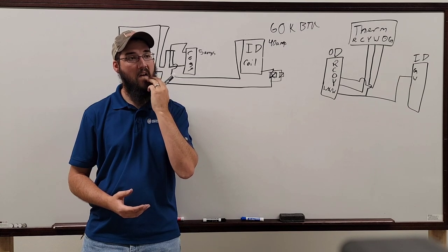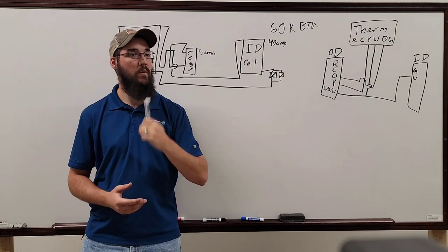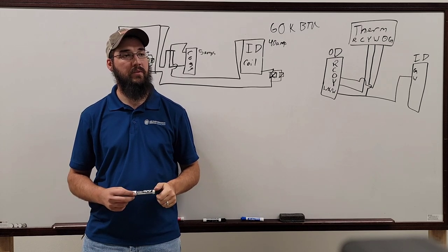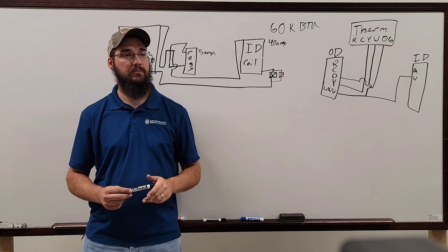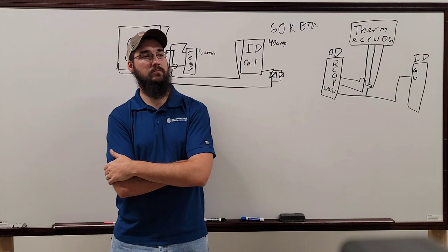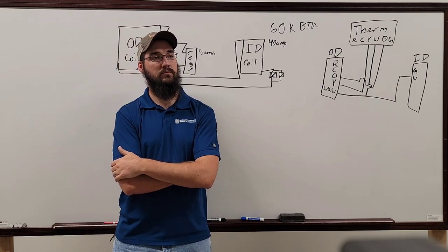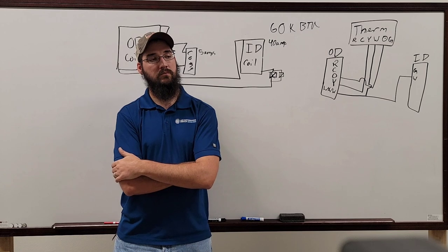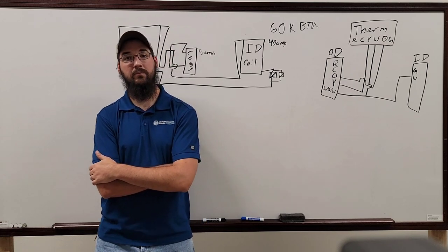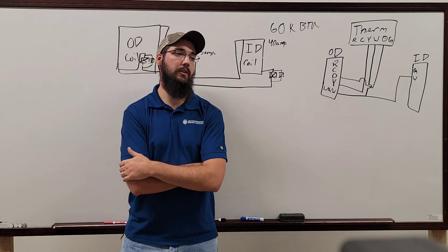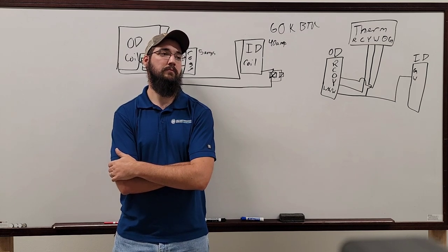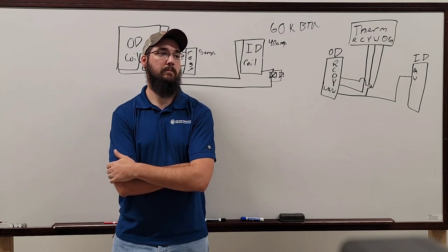Since I started doing ACs, I get a call every year from family members. Not working. Is it frozen solid outside? Yeah, it's a constant thing. I don't know if it's just the older models or if it's the thermostats, but I guess with cheaper thermostats or cheaper heat pumps, I've seen it where they won't switch over automatically. They just turn it to a block of ice and it gets cold in the house. Sometimes it's the reversing valve. But I would get a call every year, and it's like, just go to your thermostat, put it in emergency, call me in an hour.